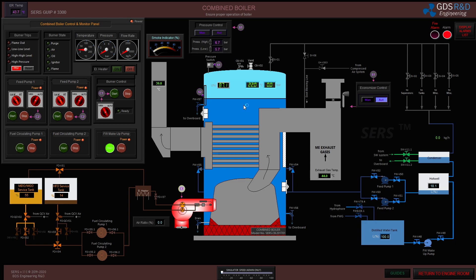I have filled up the boiler with fresh water and now I will start building up pressure. I'm going to close the vent valve and line up the fuel oil system for the burner. I'm going to start the burner with diesel oil, lining up fuel pumps, and I will start fuel circulating pump number one.